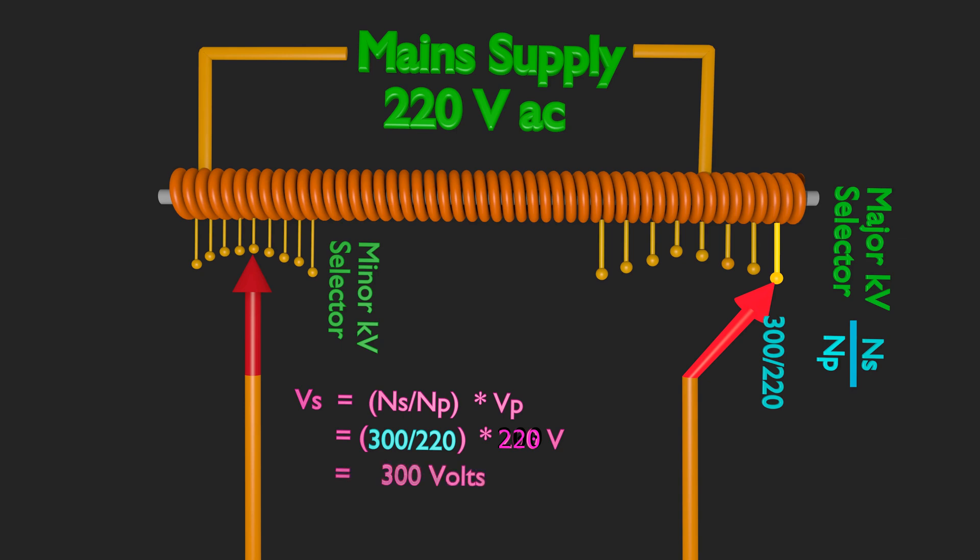Let's consider when first tapping of major selector is tapped. Number of turns in secondary divided by number of turns in primary. For first taping, turn ratio be 300 by 220. Voltage across secondary of a transformer, as per transformer law is ratio of turns in secondary to primary multiplied by voltage across primary. Primary voltage applied is 220 volts. On multiplication we get 300 volts.